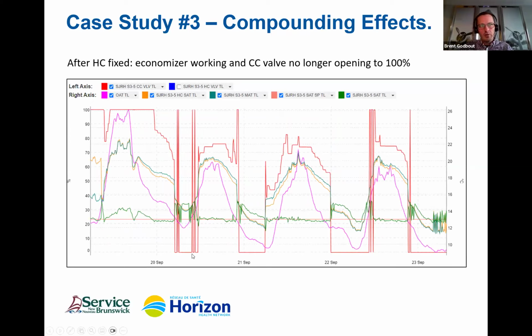And that's when we were using the free cooling. So that outdoor air in New Brunswick overnight in the summer will go down to 10, 12 degrees, and we can just bring that in to meet our set point, unload our chillers, and our cooling coil valve just shuts off. And that's what's happening here.